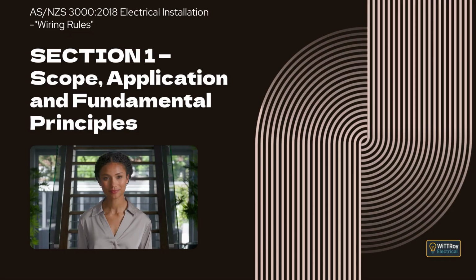Clause 1.5.5.3, Protection by automatic disconnection of supply. This clause goes deeper into how automatic disconnection works. The main idea is that if a fault happens, the touch voltage rises on exposed metal parts. We need to limit that voltage and we need to cut off the power quickly. To do this, all exposed metal parts are bonded together and connected to earth. This keeps the metal at the same voltage, which reduces the shock risk.